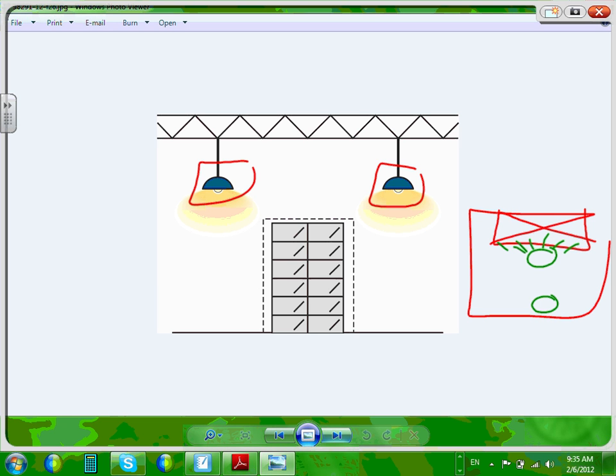In 2011, they came and said you can't have an occupancy sensor here. These lights in a closet cannot be controlled by auto means only. You can have an occupancy sensor as long as you have a switch right here that overrides the occupancy sensor. So Nick, an electrician, walks into the electrical room, turns the switch into manual, puts the fixture in manual mode, works on the equipment. When you're done, put it in auto, meaning the occupancy sensor is controlling it, and get out.